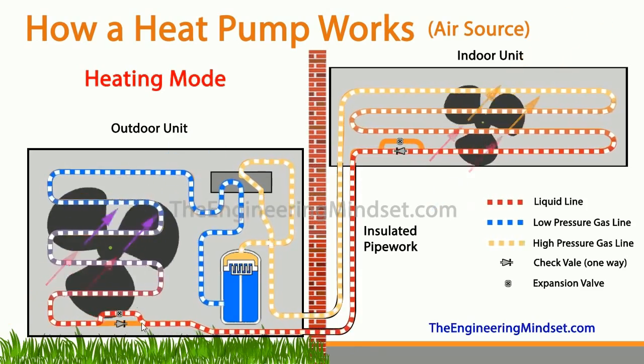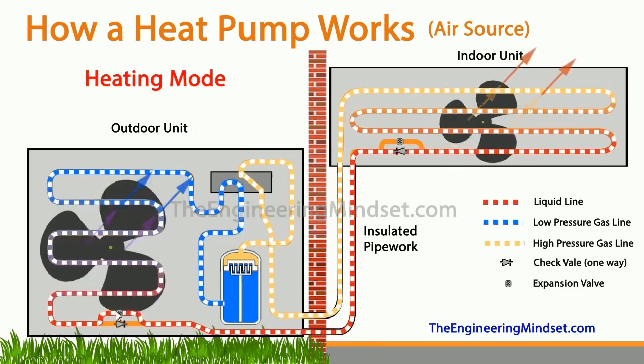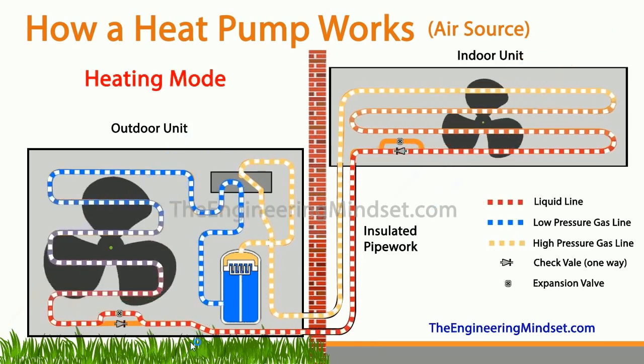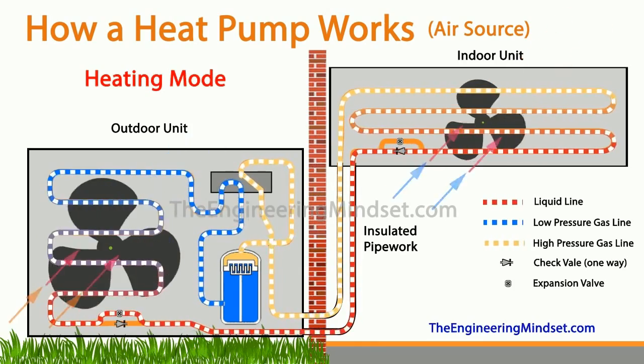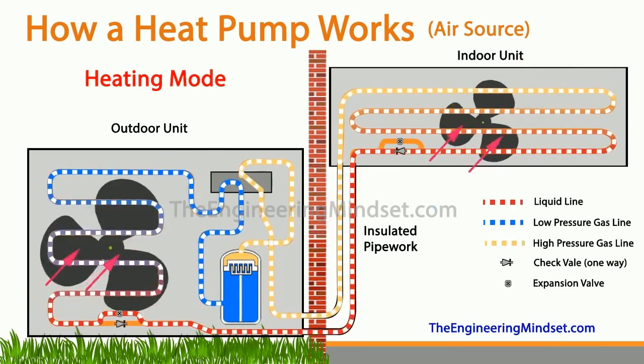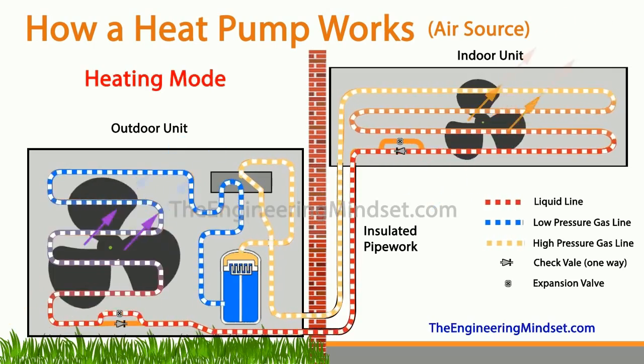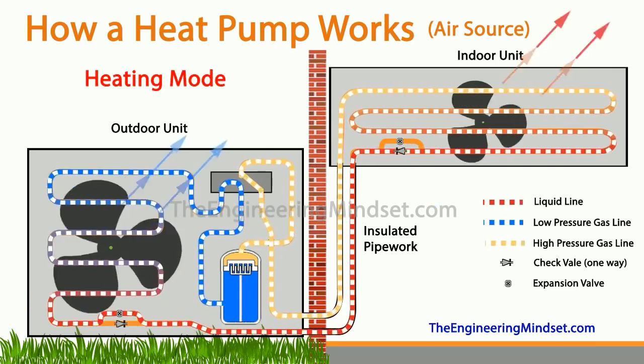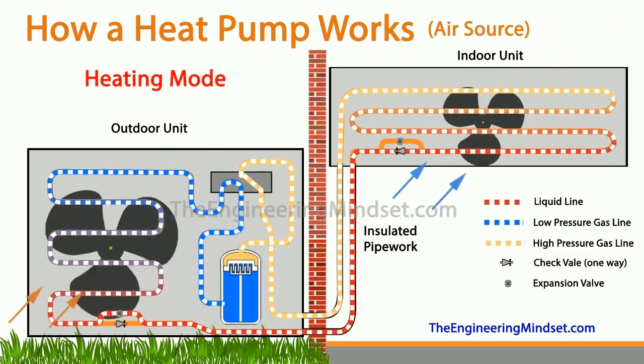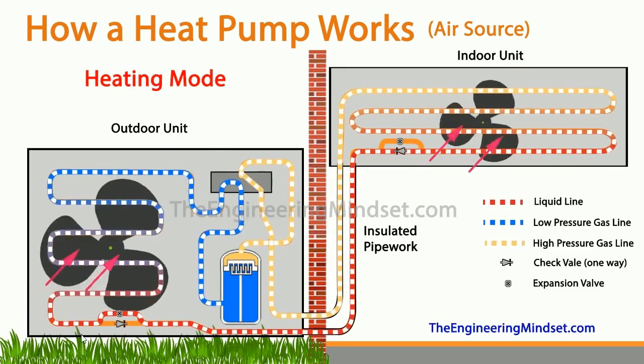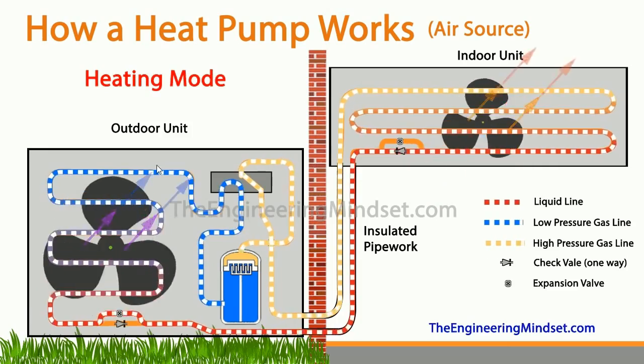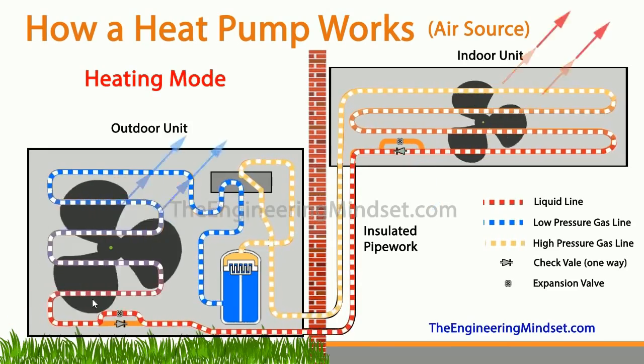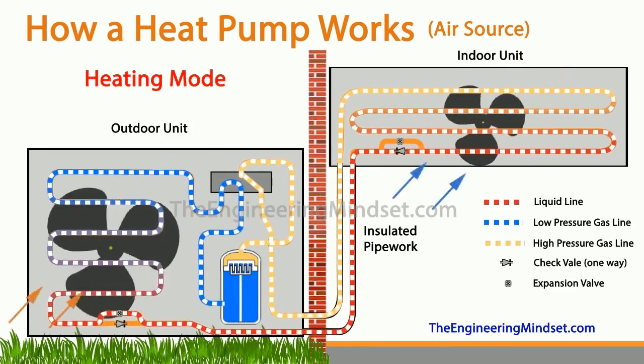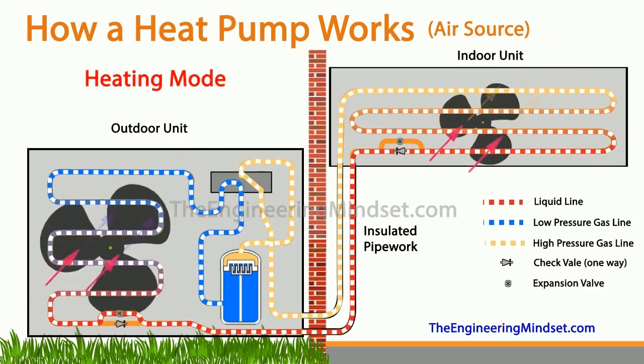And you can see here the check valve will not let that pass, so it's going to go through the expansion valve instead. The expansion valve expands the refrigerant, and when that refrigerant passes over the expansion valve, it's going to leave as a low pressure, low temperature liquid vapor mixture, and it's being pushed through this coil all the way to the other side, and it's going to pick up some of the heat from this air that's being blown across it by the fan.